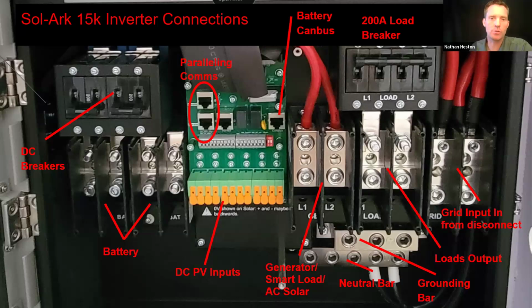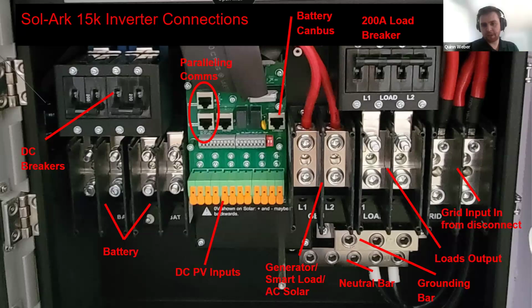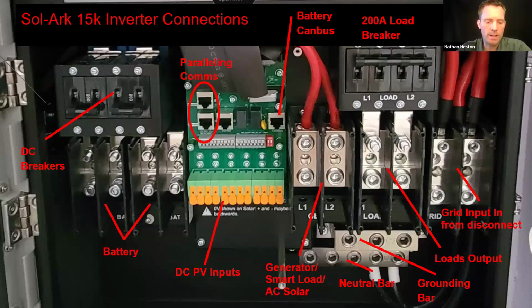What are we looking at in terms of our grid input here? So that's a 200 amp connection, right? For the 15K, yes, exactly. That's a 200 amp connection. And that loads breaker there that we can see, that's also 200 amps. Yep, 200 amp for the loads. And then for the AC coupling, it's up to I believe 90 on the 15K. And I think that gives you 19 kilowatts, I believe, of continuous input on that.